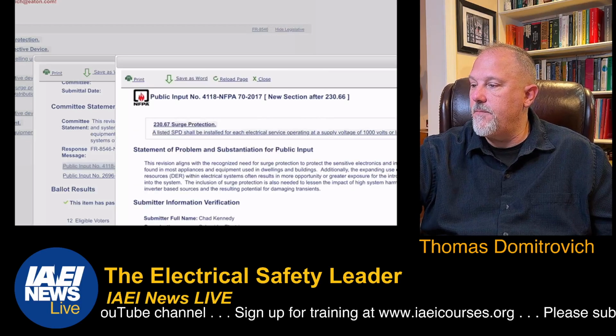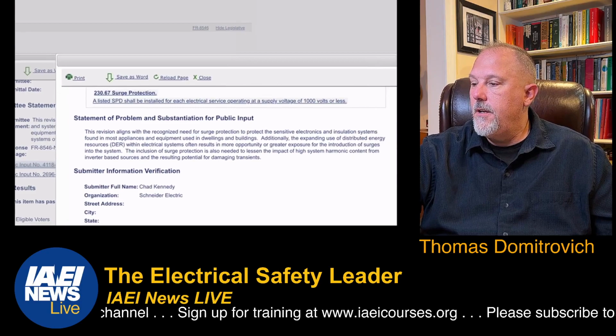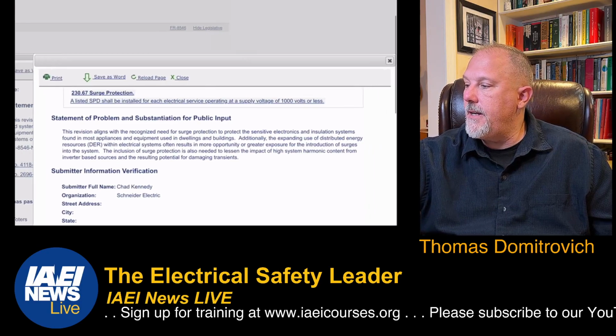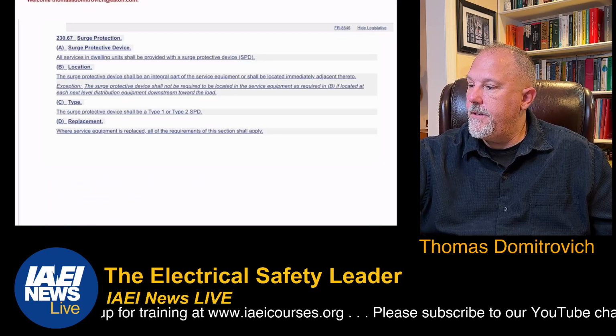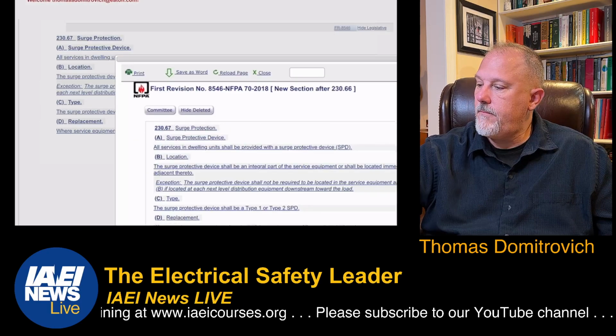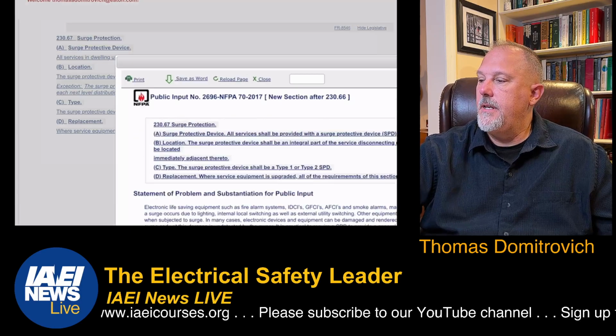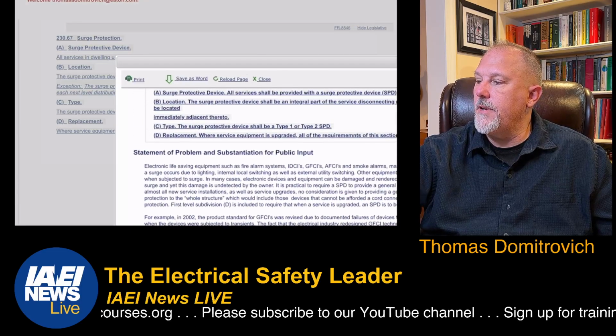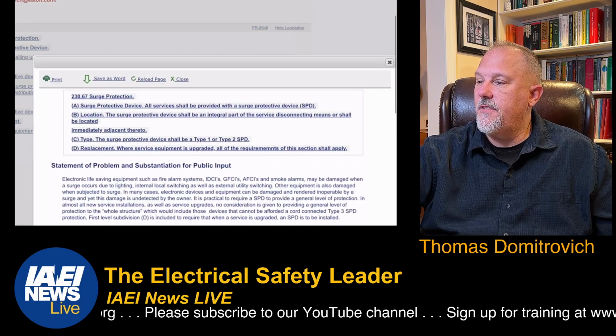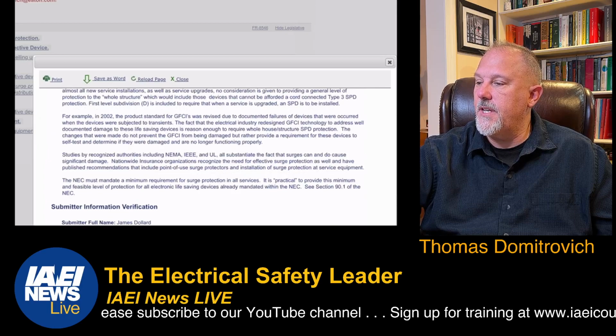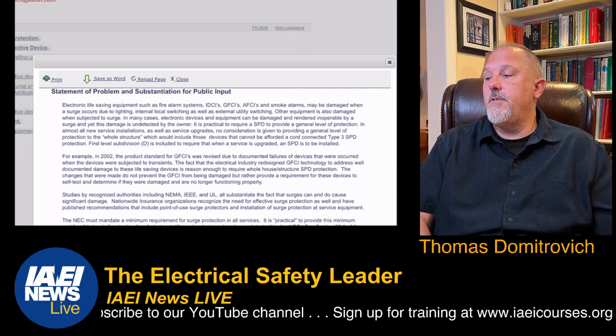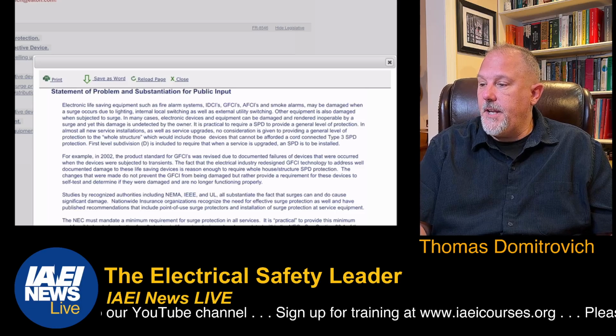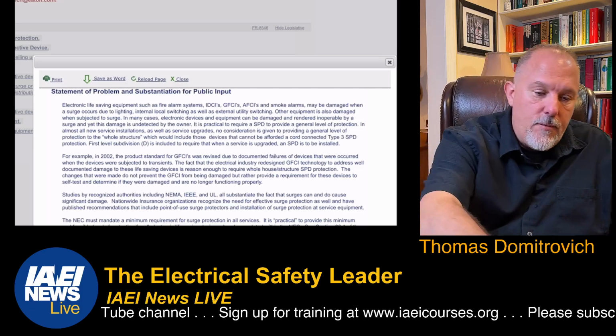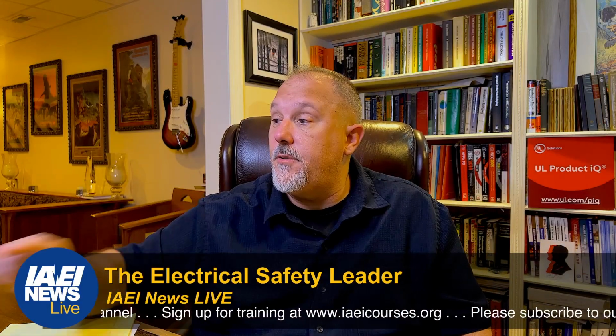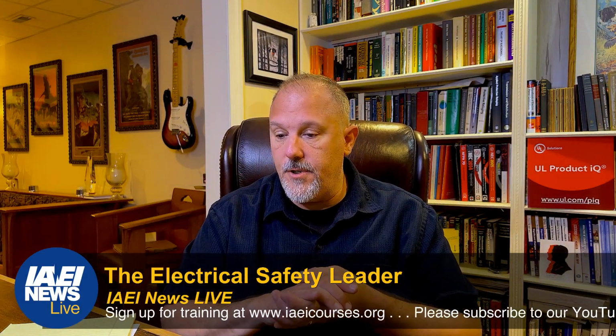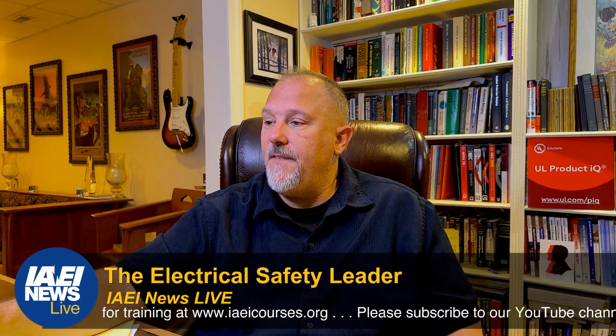The first one came from Chad Kennedy and Schneider. The original aligns with the recognized need for surge protection. Let's go back to the first revision and look at the second public input. This one came in from James Dollard, Local 98, IBEW, on surge protective devices, all surge device type 1, type 2. It looks like Mr. Dollard gave studies and examples, etc. So that's sort of the history and how you can find some of the information around surge. So we had it for dwelling units.